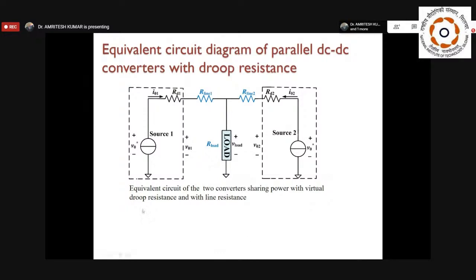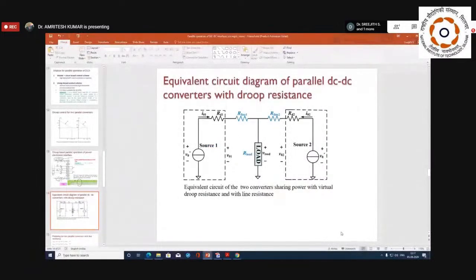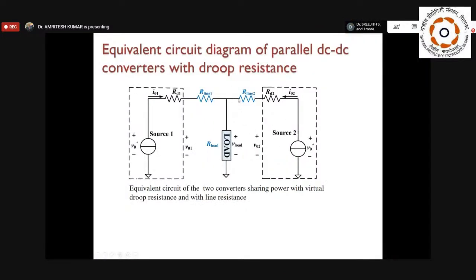So basically this V0 star that you can see here is the reference voltage that you try to maintain as 250. This RD1 is incorporated as a virtual resistance. Actually, this is not the line resistance, this is a virtual resistance that I have connected. So from V0 star, if you subtract the drop across RD1, you will arrive at V01, the terminal voltage of one converter. Similarly, for converter 2, again the same reference voltage is given. Again, you can have the same line resistance or different line resistance, that's an assumption. These two converters in parallel are feeding a common load.